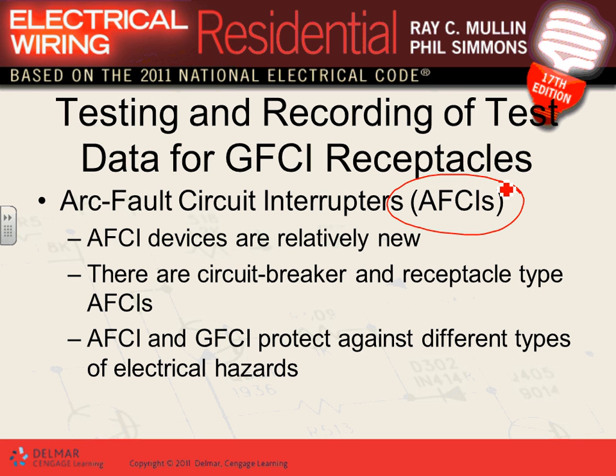So pushing things around. Now, what happens if you damage a conductor, guys? A cord got damaged, and it's damaged enough that you have an arc between a hot and a neutral, or a hot and a ground. That arc could escalate into a fire before the circuit breaker wakes up. It could be in a cord, or it could also be inside the receptacle, or inside the light or fridge. Because of that, the people smarter than us came up with the arc fault circuit interrupter.